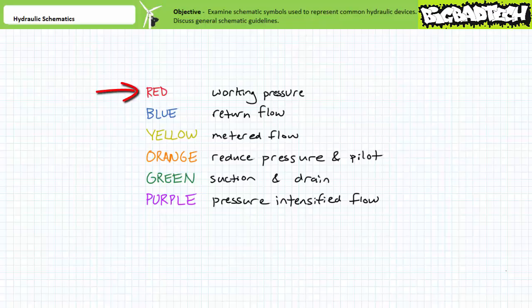Anyways, red is used to represent fluid at working pressure from a pump to a device. Blue is low pressure return flow. Return flow is ordinarily bound for the tank. Yellow is metered, controlled, or restricted flow. An example of restricted flow would be after a flow control valve or restriction. Orange is pilot or reduced pressure flow.